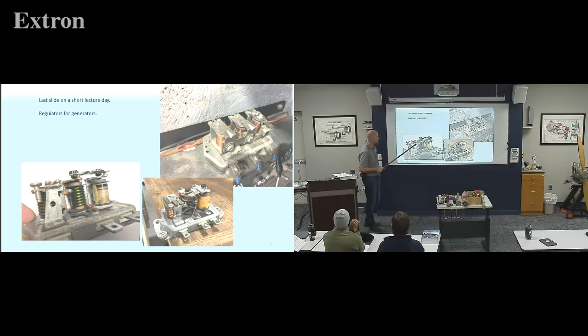And the reason it opens back up is it's spring open to begin with. So if you look at these just sitting here, before I put any power to them, it's spring open. So I'm not going to be able to make power and actually send my power through here. But what happens is, as the generator is starting to spin up and we start to produce a voltage, there's a tiny little coil underneath the big heavy guy - when I say tiny coil, it's a thin wire. If you look at these, a lot of times you can find where the thin guy pops out underneath the big one. Dean likes to call him the wimpy man.